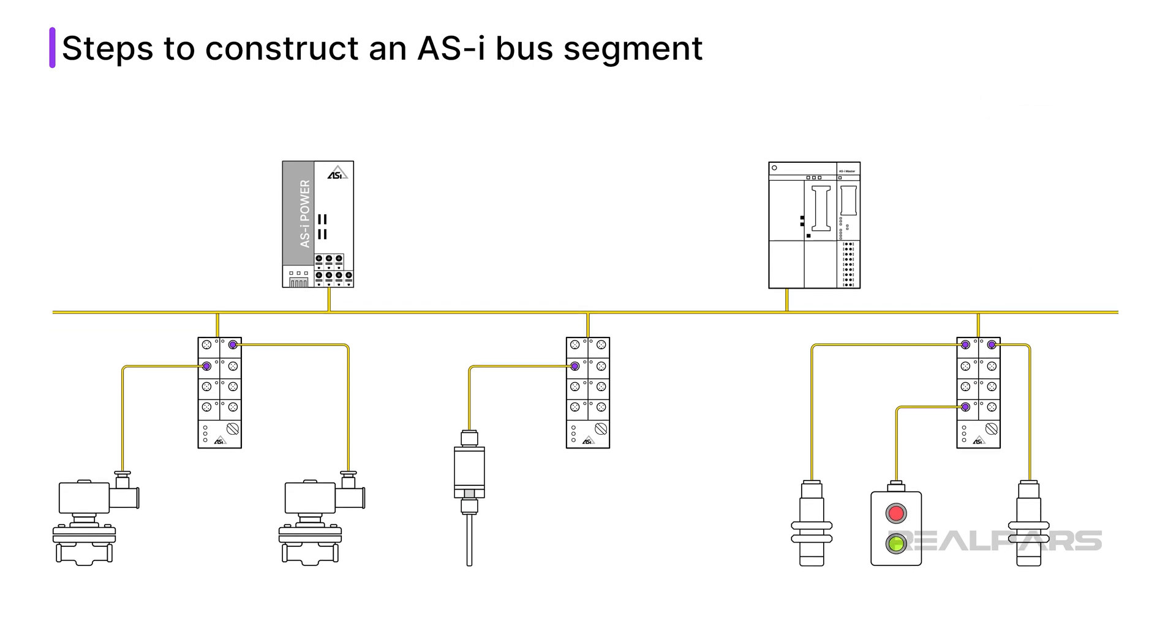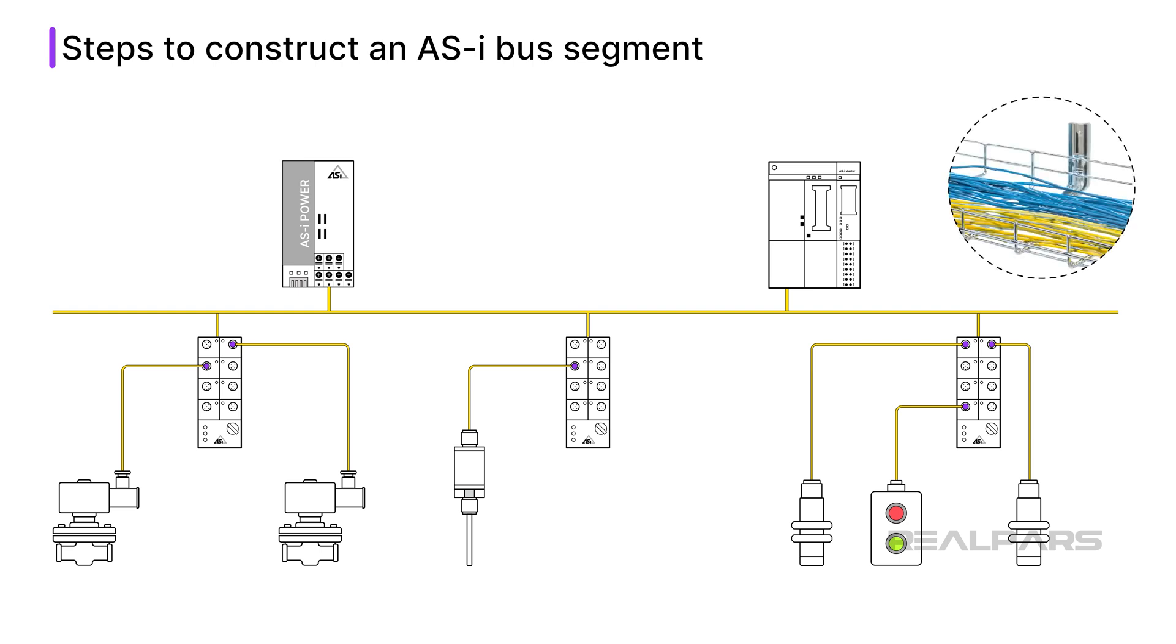Now, I will install the cable. I choose to use basket tray to support the cable and keep it away from sources of electrical interference, such as motor cables. Having support, such as basket tray or conduit, physically protects the cable from damage.